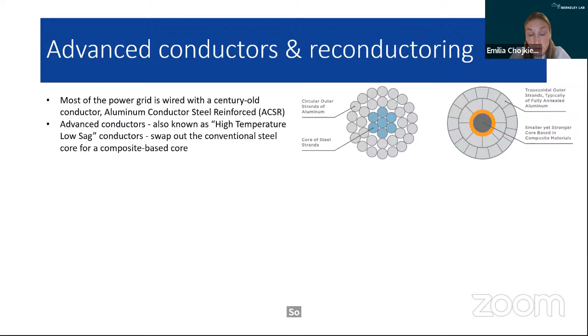These conductors are also known as high temperature, low sag conductors in many places of the world. That composite core allows the conductor to operate at higher temperatures and fit more aluminum, achieving around a 2 times increase in capacity. These advanced conductors have so far mostly been used in reconductoring projects, which replace a transmission line's existing conductors with these advanced conductors within an existing right-of-way, utilizing existing towers and upgrading terminal equipment as needed.